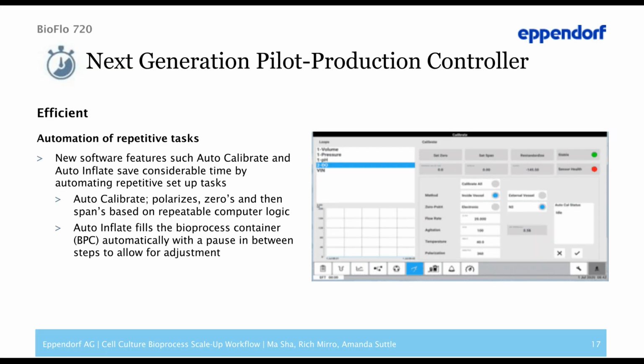If I switch to the second principle, efficiency, the new software and instrument feature additional software, auto-calibrate and auto-inflate, both of which are designed to save considerable time by automating repetitive tasks. The auto-calibrate polarizes, zeros, and then spans DO sensors based on a repeatable computer logic.